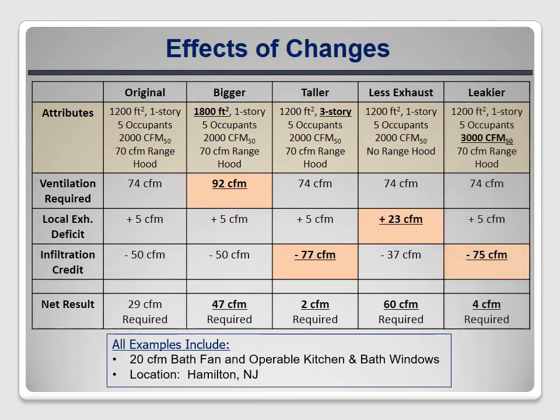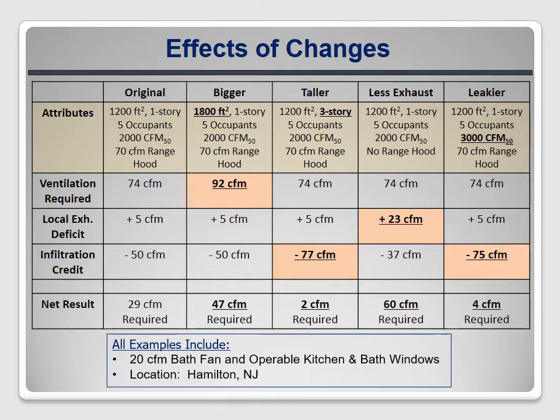Finally, if the house is leakier — with a blower door result of 3000 instead of 2000 CFM at 50 pascals — the infiltration credit goes up from 50 to 75 CFM, reducing the required fan size to only 4 CFM. It might seem silly to install a fan for just 2 or 4 CFM, and the 2016 version of ASHRAE 62.2 addresses this by adding a statement that if the calculated fan flow requirement is less than 15 CFM, a system doesn't need to be installed. Some programs may have adopted this requirement for earlier versions of the standard — check with your program staff to find out.